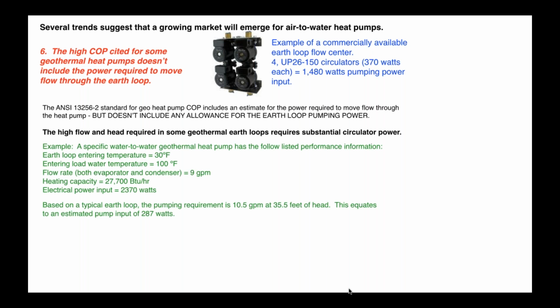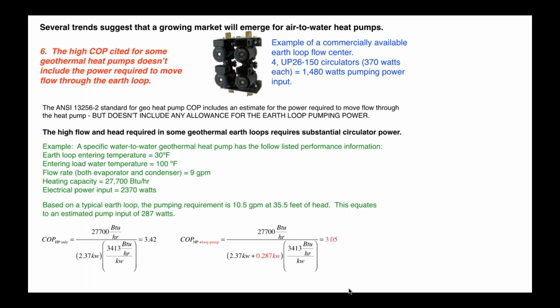Another thing, I'll just turn all this on. Again, I'm going to encourage you to get the PDF and read this through in detail. But oftentimes the COPs that you see in literature for geothermal heat pumps do not include the power to operate the earth loop circulators. Or if they do, there's a certain ANSI standard that's mentioned here. I've looked at that ANSI standard in detail. There is a calculating procedure to get an estimate of that power. In my opinion, it's not accurate. They're only looking at the pressure drop through the heat pump, not the pressure drop through the earth loop.